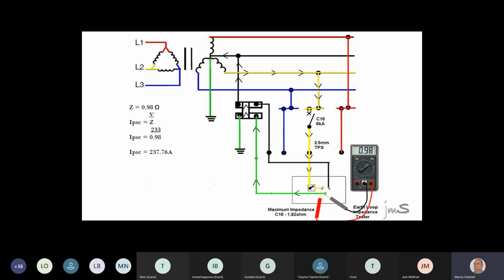And guys, be warned, in a theory exam, they can ask you to work out the prospective short circuit current. They can ask you to take the voltage divided by the impedance. If the voltage is 233, have a look there, 233. That voltage we call measured voltage. You can't just say 230. It's real voltage, because voltage will fluctuate all day, every day.